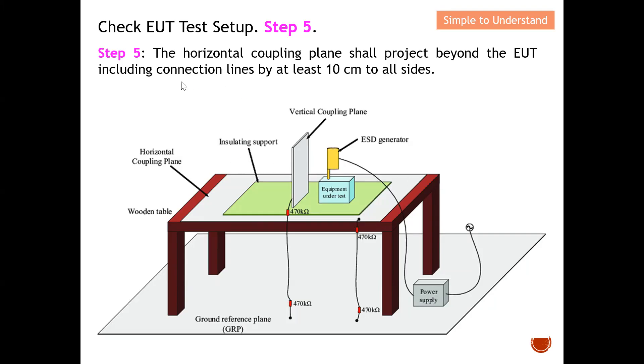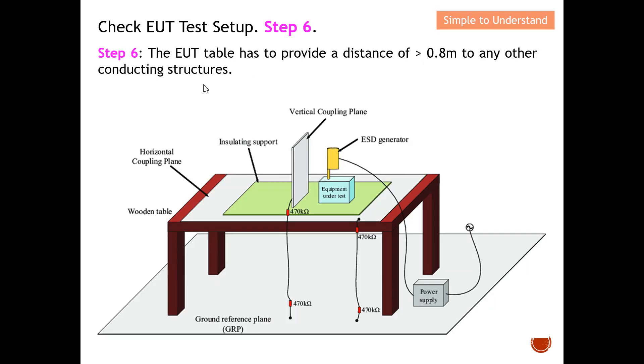Step number six: the EUT table must provide a distance of 0.8 meters to any other conducting structure. Anything that is conductive must be at least 0.8 meters away from your EUT table in order to comply with this step.